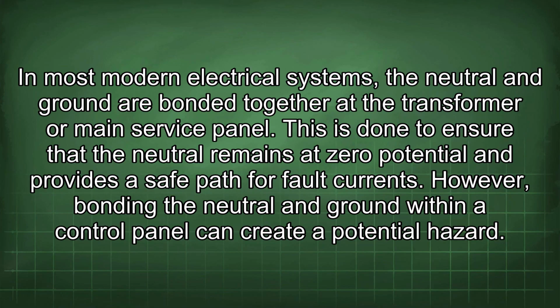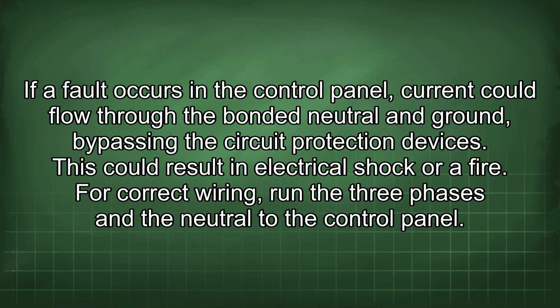In most modern electrical systems, the neutral and ground are bonded together at the transformer or main service panel. This is done to ensure that the neutral remains at zero potential and provides a safe path for fault currents. However, bonding the neutral and ground within a control panel can create a potential hazard. If a fault occurs in the control panel, current could flow through the bonded neutral and ground, bypassing the circuit protection devices. This could result in electrical shock or a fire.